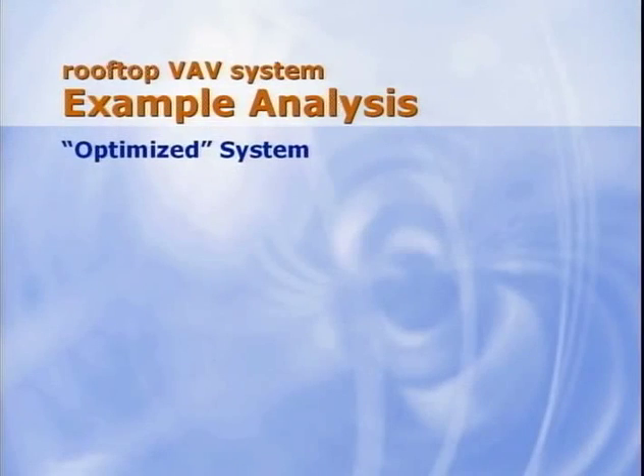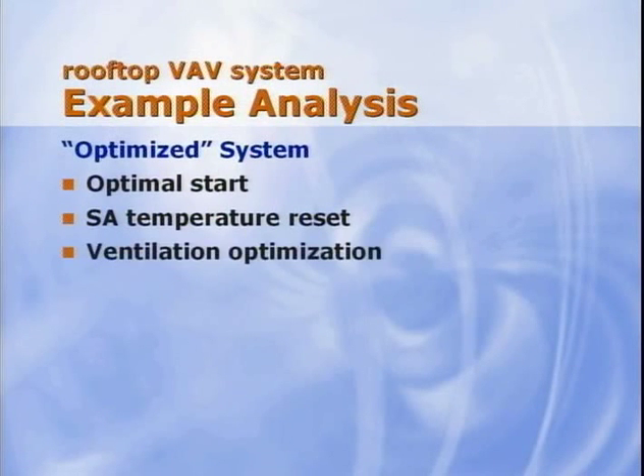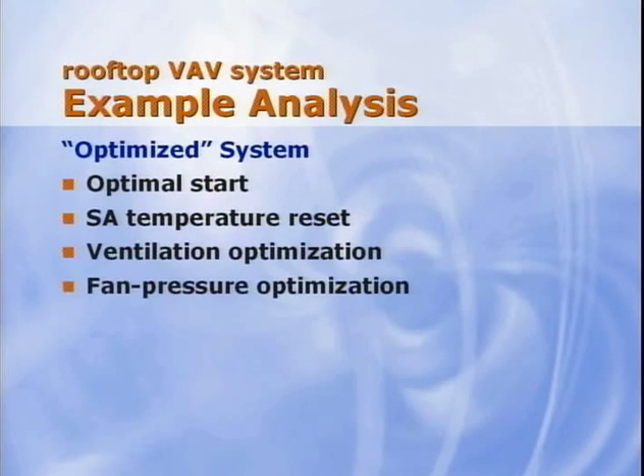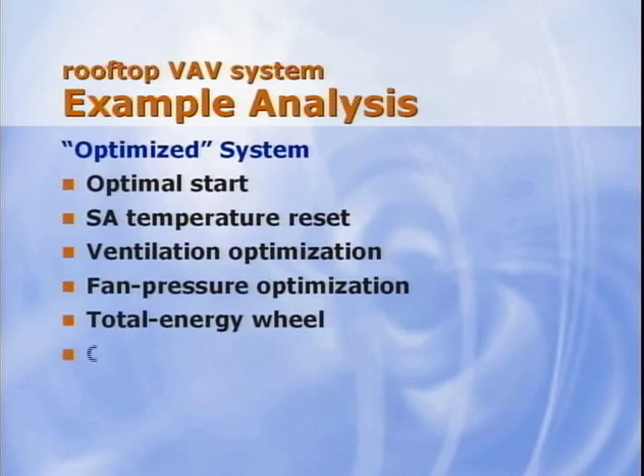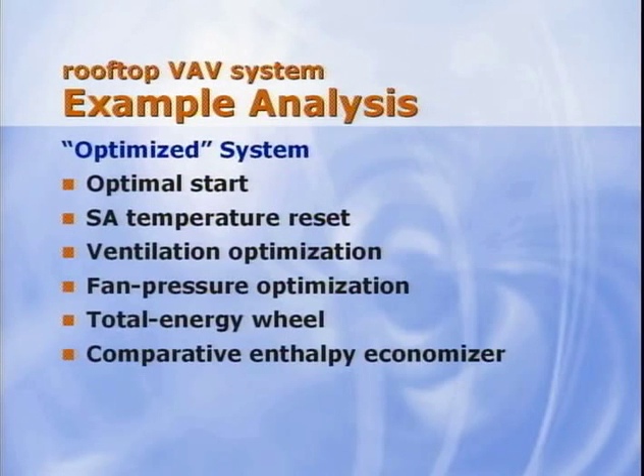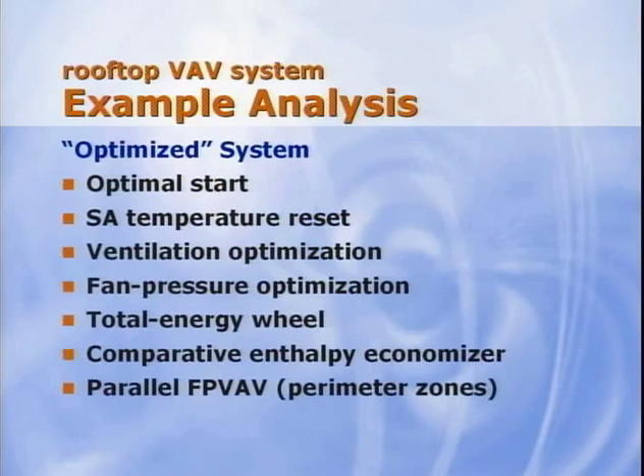to a more optimized system. For the optimized system, we added the optimal start, supply air temperature reset, and ventilation optimization control strategies we discussed today. The supply fan is controlled based on fan pressure optimization rather than on a fixed set point in the ductwork. The rooftop unit contains a total energy wheel to precondition the outdoor air and uses comparative enthalpy economizer control rather than fixed dry bulb control. Finally, the perimeter zones are equipped with parallel fan-powered VAV boxes rather than VAV reheat boxes.